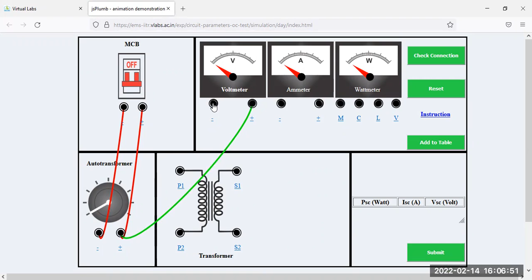From this point to the ammeter positive terminal, and the negative terminal of this ammeter is connected to the M terminal of the wattmeter. L and C you may just connect here, and from this L point go to the positive polarity of the HV winding. So this one is your HV, and negative polarity from the HV winding to this V terminal of the wattmeter. And this one is to short the LV winding, so just short these two terminals, connect these two points.